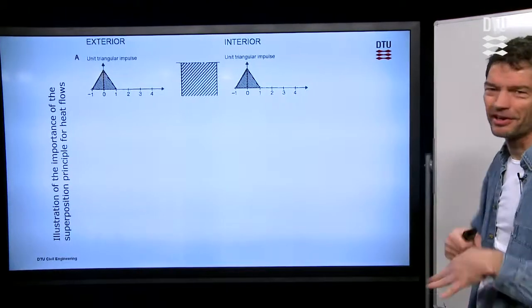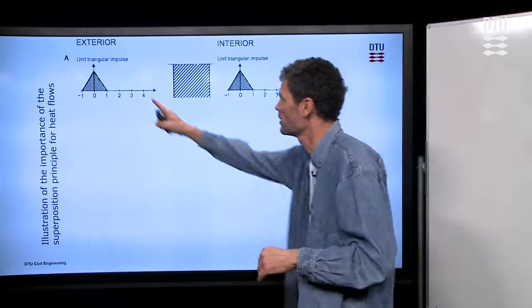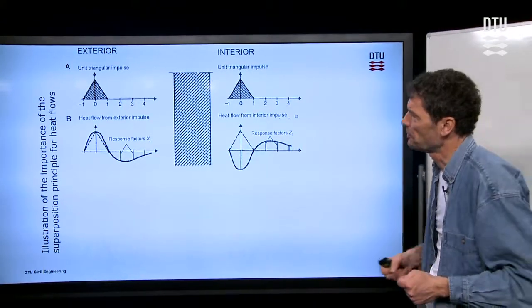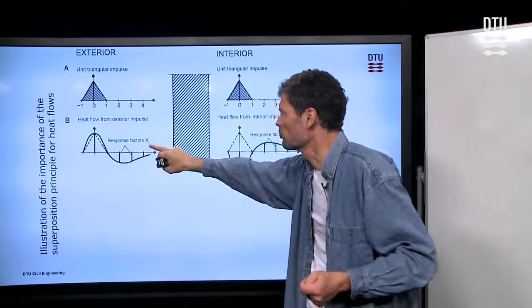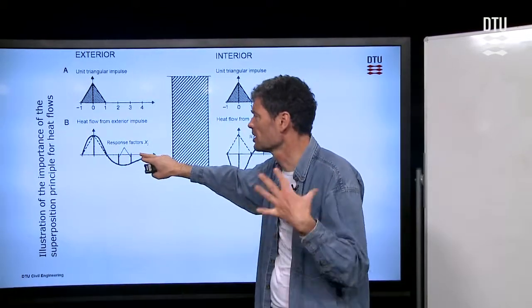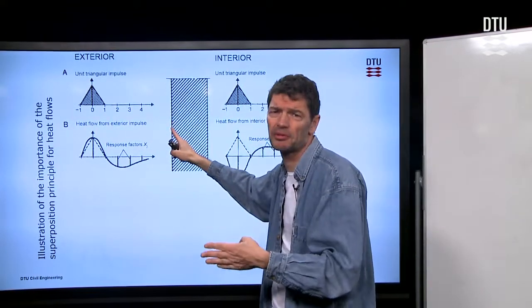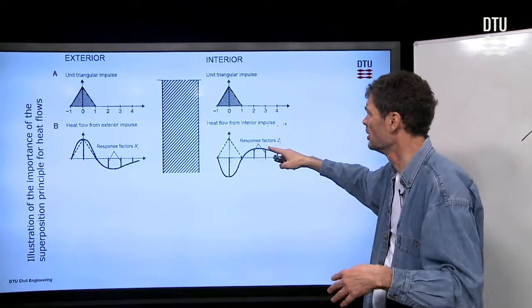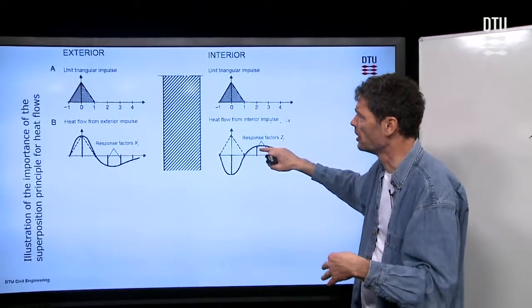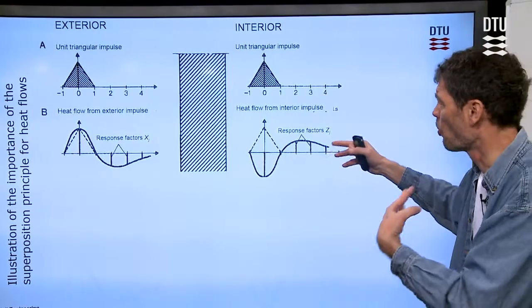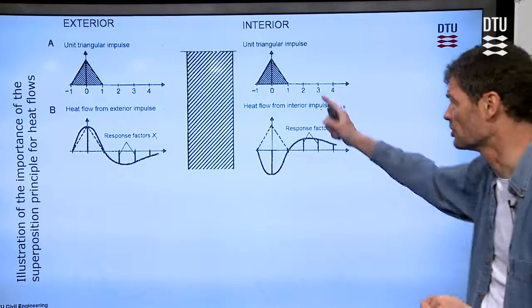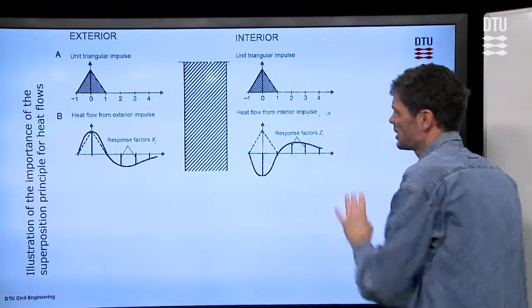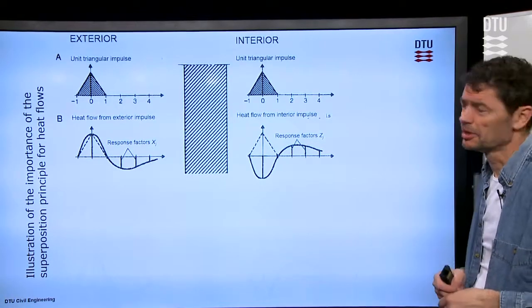So now let's look to the whole methodology of calculating this. So we work with these triangular impulses. Let's assume that we could have one coming from each of the sides of the wall. And if we look to the first impulse that came on the left hand side, then we have some response factors. And the X factor tells us what is the heat flow coming into the left hand side of the wall as a result of the temperature impulse on the left hand side. We have also a response factor on the opposite side. So the Z factor is the response factor for the temperature on the right hand side.